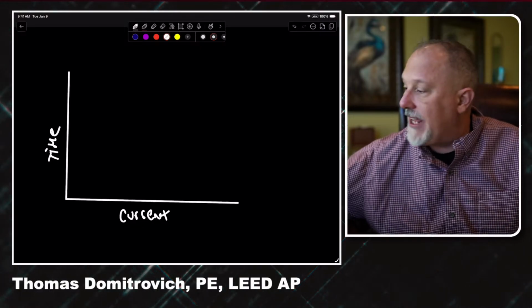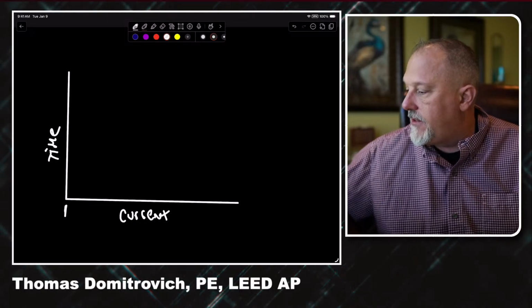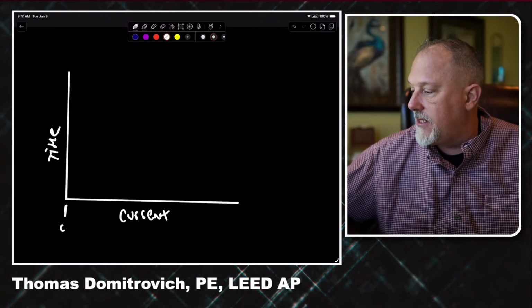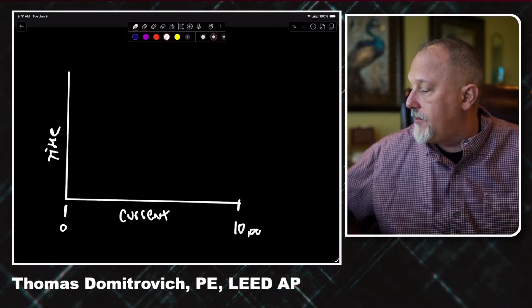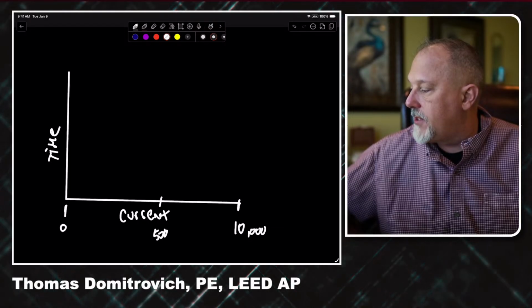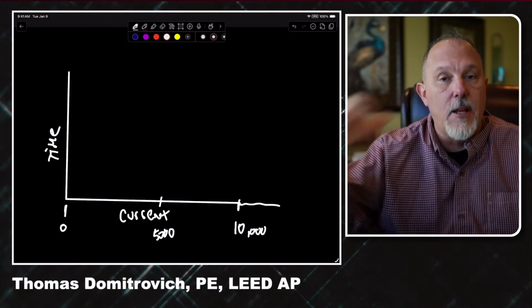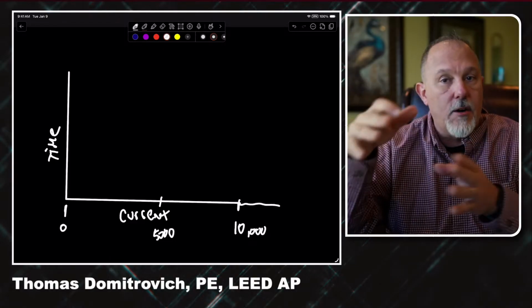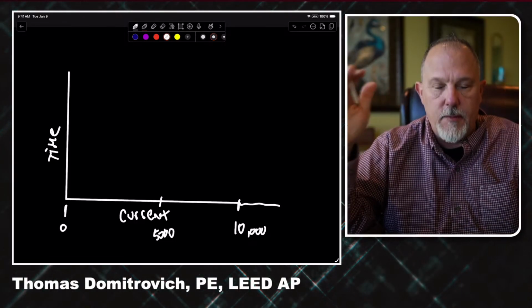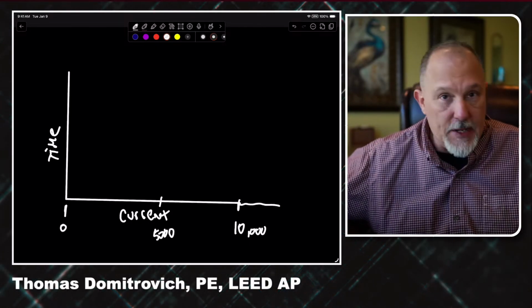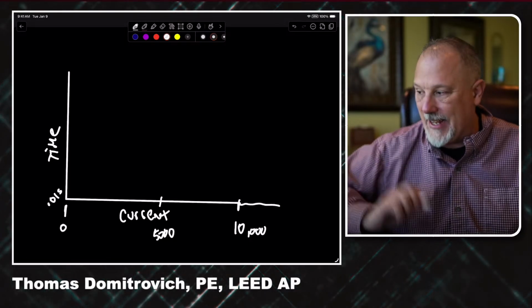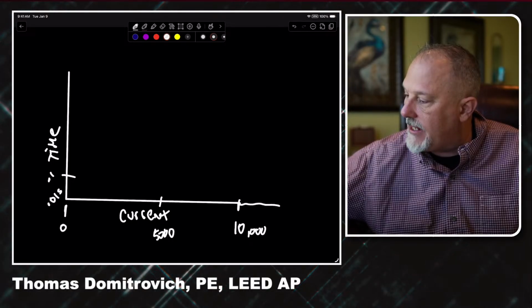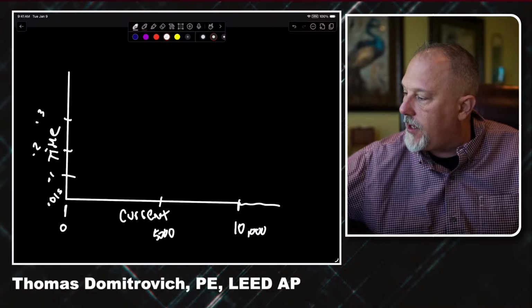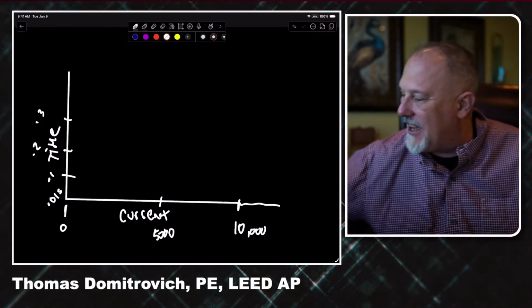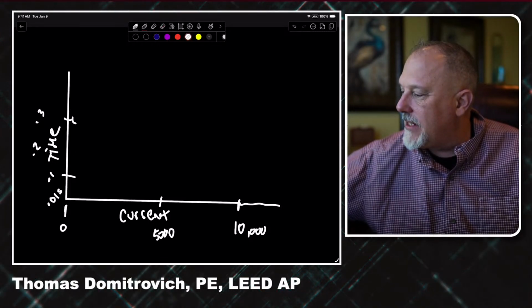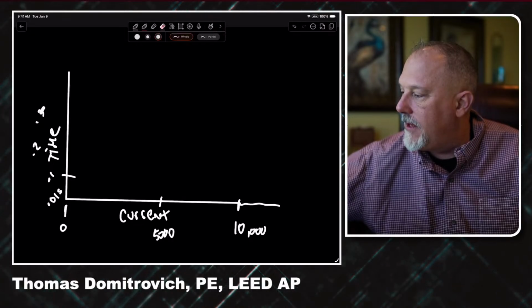So let's say, for example, since this is current, let's say that this is 0 amps, and let's say this is 10,000 amps, and we'll say this is 5,000 amps. All right. Now keep in mind it's log-to-log paper, so the increments, the distances, are off on log-to-log type paper. So just be mindful, you might see that. In time, typically we start at 0.01 seconds. And then you'd see 0.1 seconds, then 0.2 seconds, 0.3, etc. Well, they're much closer together. I got a little aggressive there. Hold on. Let me delete that.